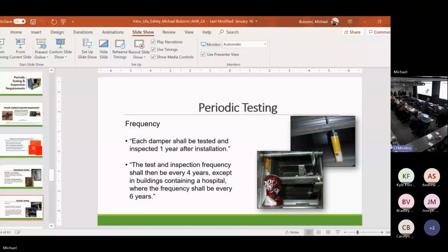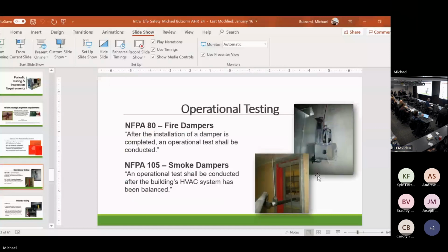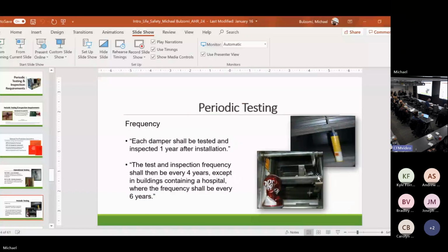And these are the little pictures of things we find. I have to point that out. So I've got a block. Here's my actuator sticking out of the wall. That's not correct. Here's a pipe running through a fire damper. Everybody here is just as bad as the IT guys. I've got a Coke or Dr Pepper can. Somebody forgot their tube of caulk. And why does this happen? Anybody know why this happens?